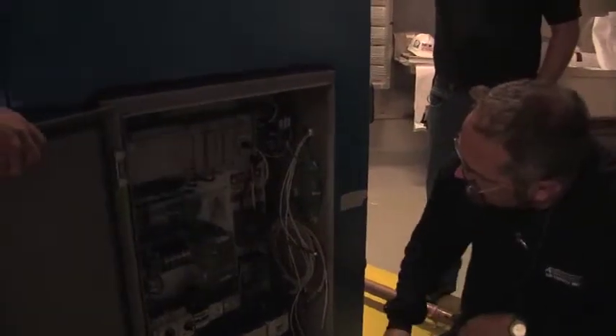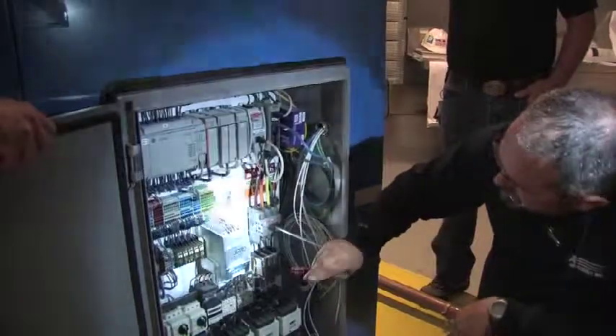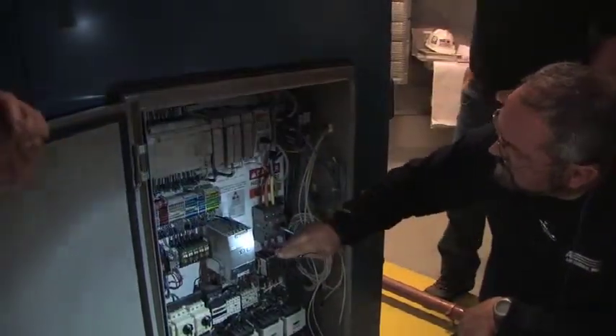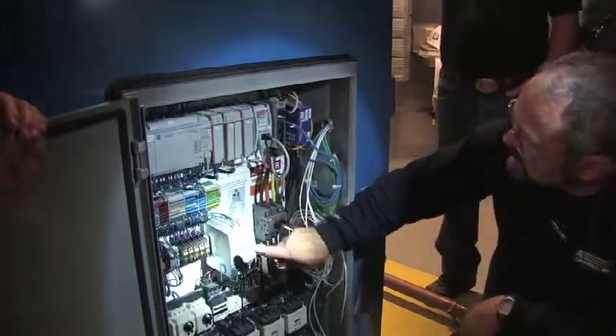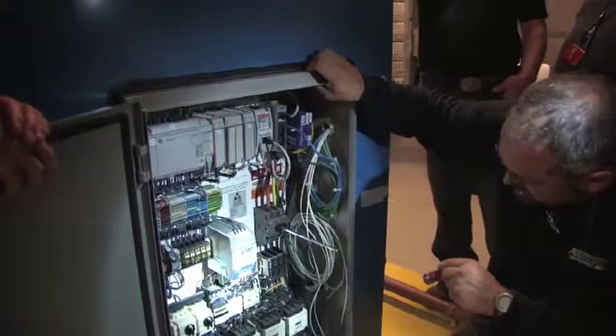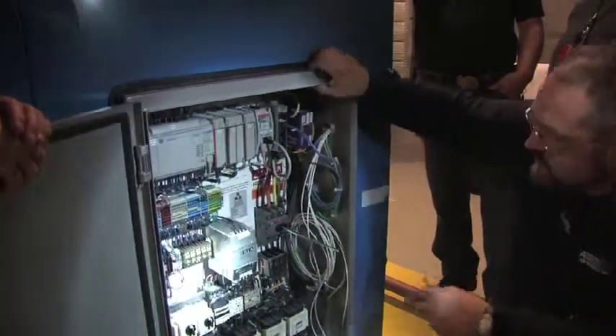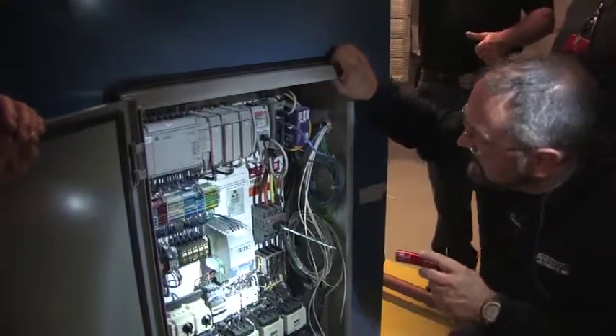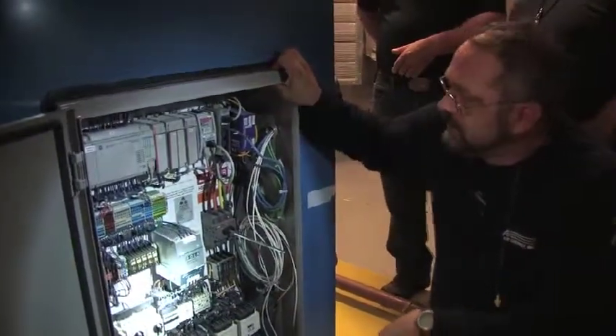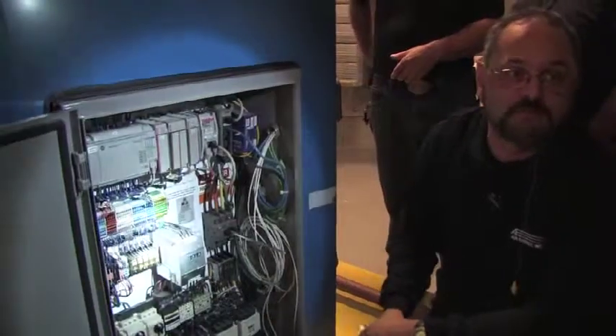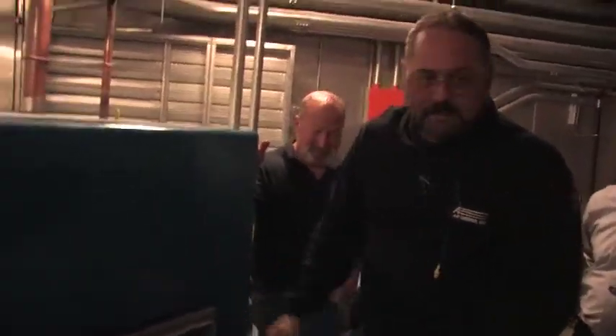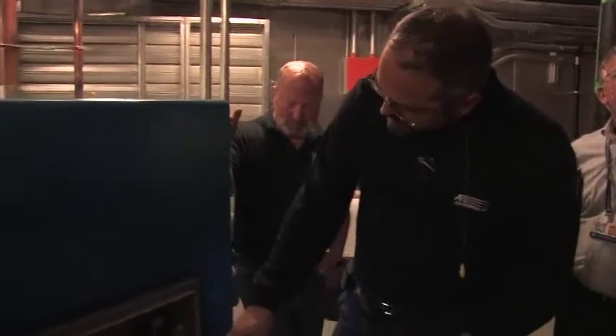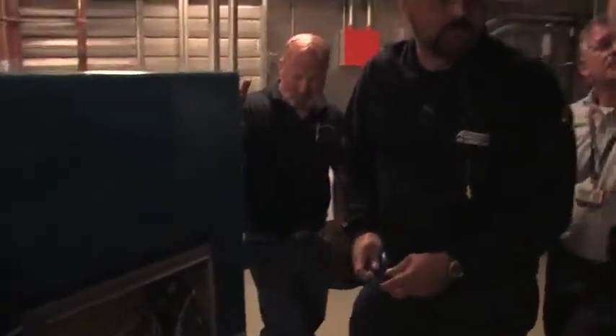Don't change it. So now, is there a reset on the 24 volt transformer or no? Nope. There is a regulator. Okay. Is there typically any issues ever with the 24 volt transformer? I haven't had any. So, if you look at the size of it, the output's 5 amps. Usually people run these things off like 1.5 amps. So they've got a really good cushion. Now the reason they go to 5 is they have a 3 amp one. The reason they go to 5 is just to run the switch and the LonWorks. All that's 24 volt. But I mean, they're really beefing it up, so it shouldn't be an issue.